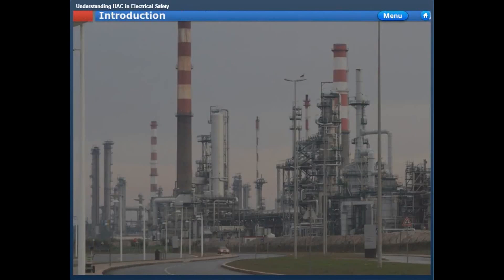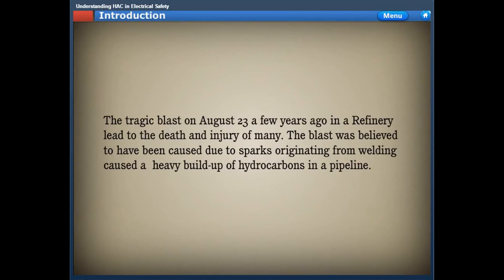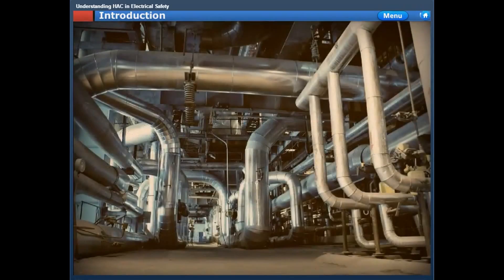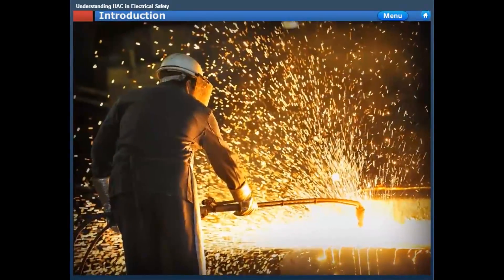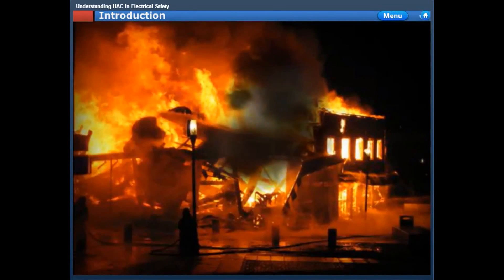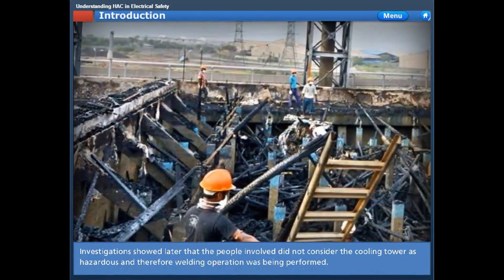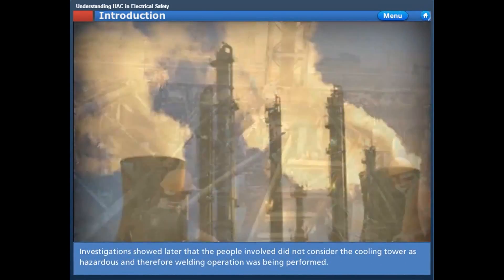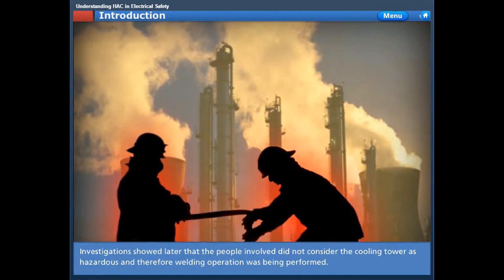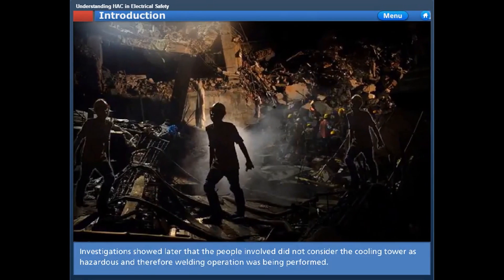The world-famous blast on August 23rd a few years ago was believed to have been caused due to sparks originating from welding, leading to heavy build-up of hydrocarbons in a pipeline. This led to the blast and collapse of the cooling tower. Investigations showed later that the people involved did not consider the cooling tower as hazardous, and therefore welding operations were being performed. The result: a fatal accident.